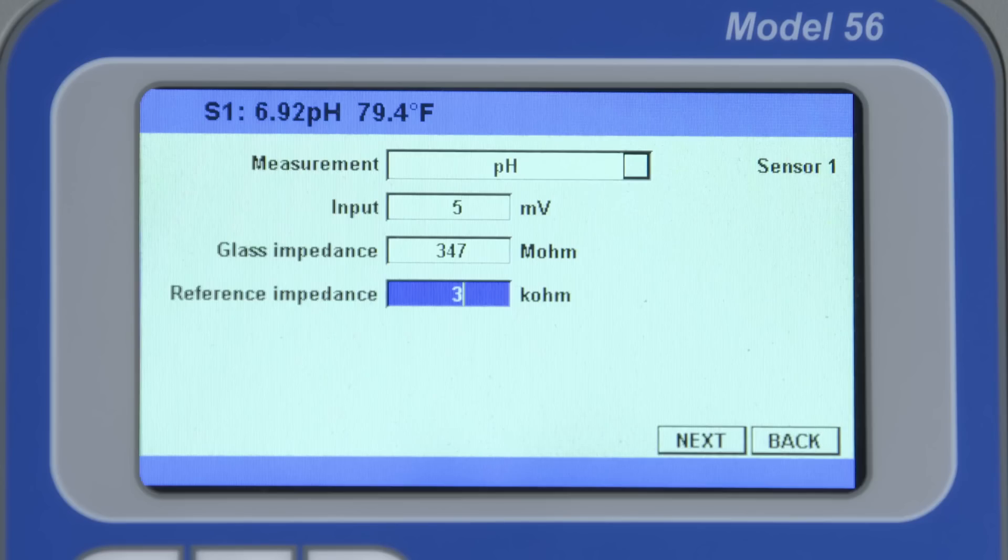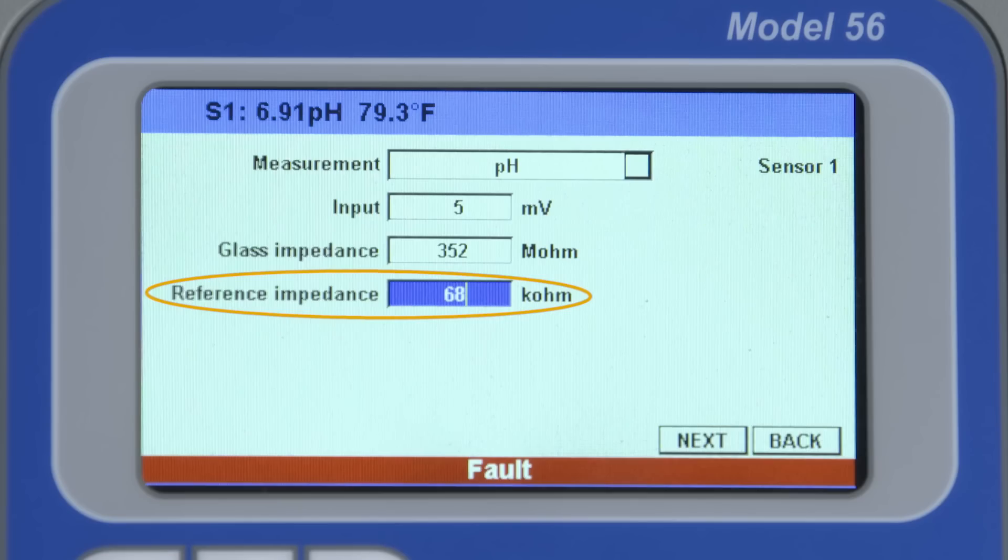A new pH sensor generally has a reference impedance of under 10 kiloohms. Over time, this can trend upwards which could indicate coating or clogging of the reference junction or depletion of the reference electrolyte.